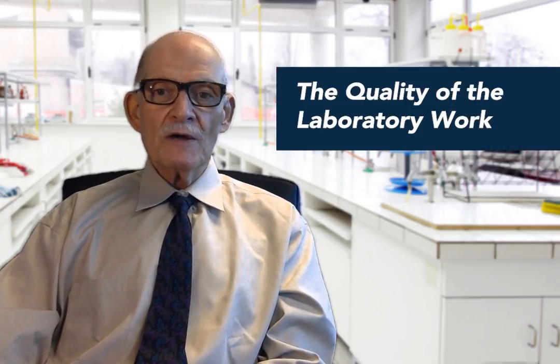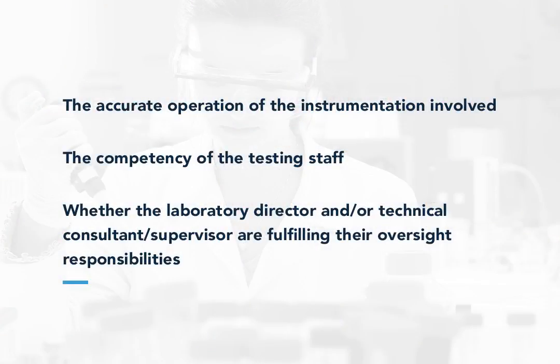When a laboratory report must be corrected and the amended results are sent to the ordering physician, questions might be raised regarding the quality of the laboratory work, such as those regarding the accurate operation of the instrumentation involved, the competency of the testing staff, and whether the laboratory director and/or technical consultant or supervisor have been fulfilling their oversight responsibilities.